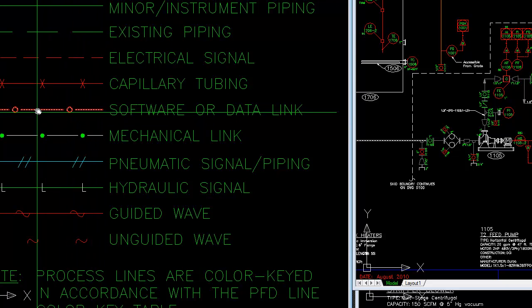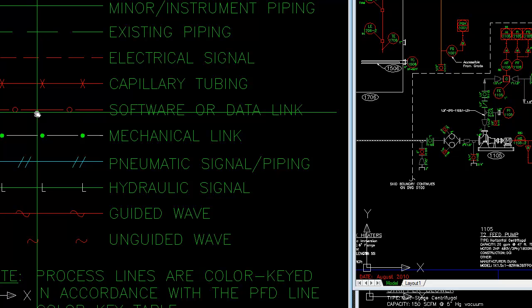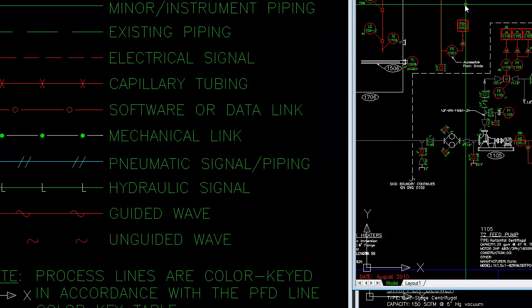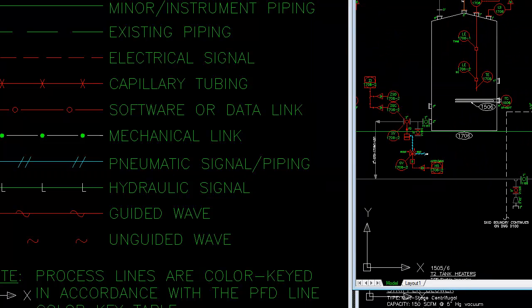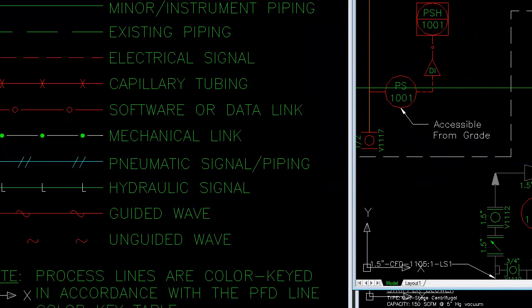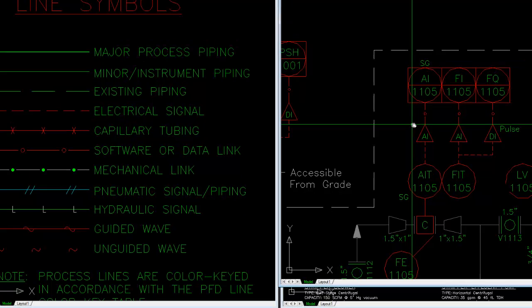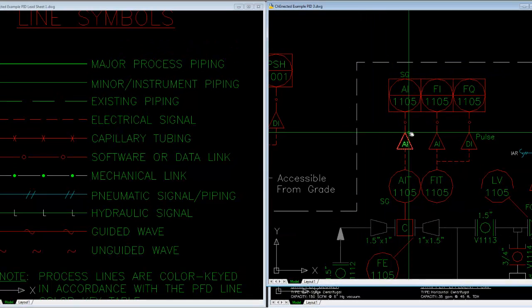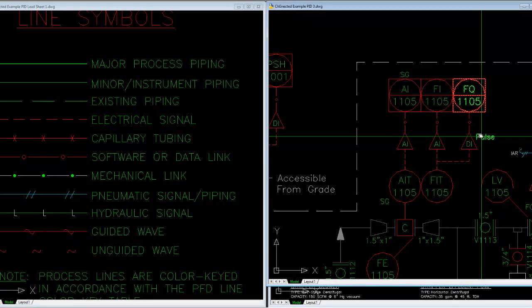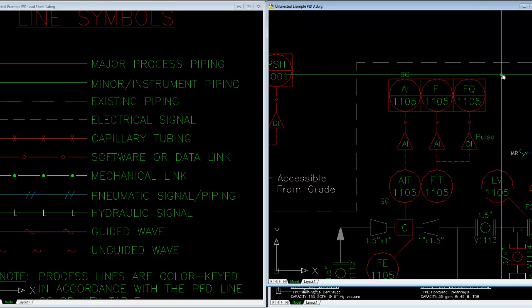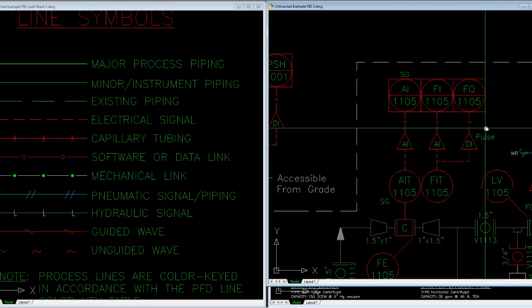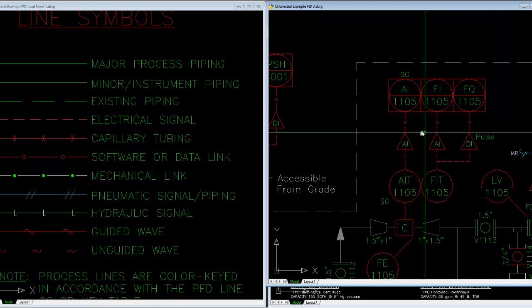That's a very abstract line, but simply it means I like to use it anywhere where there's a program that's running some code or performing some function that will result in interpretation of input or output. That's going on in software, you show that line, and we show software lines throughout the example P&IDs, generally at the break of input and output. Once a signal is physically input into the control system, and that processing is occurring inside the computer, you have software lines.